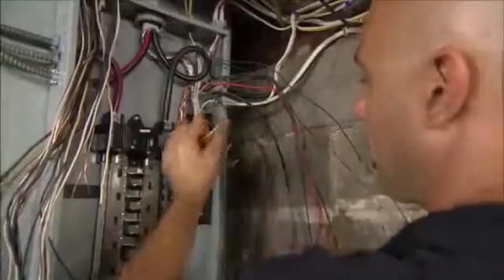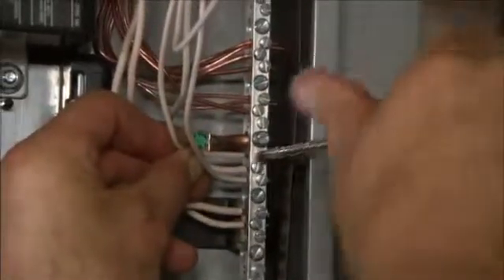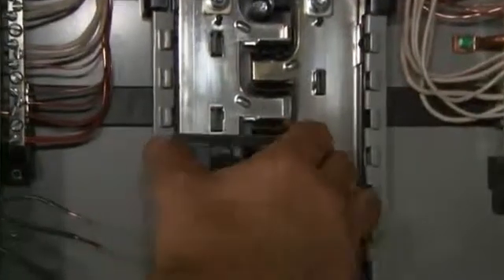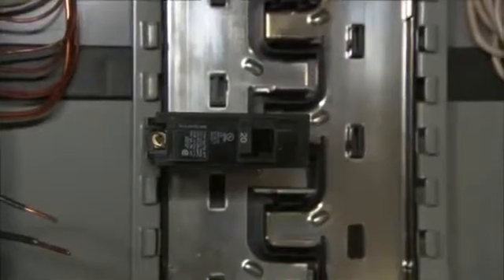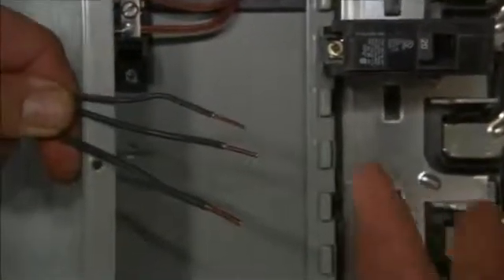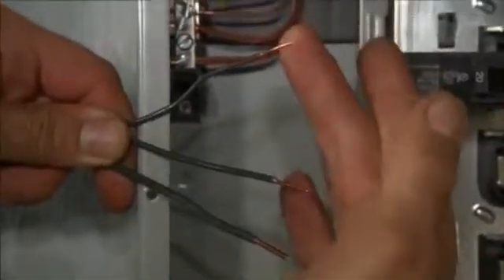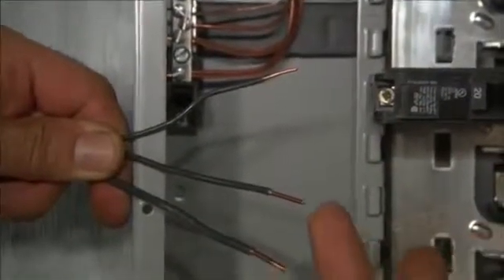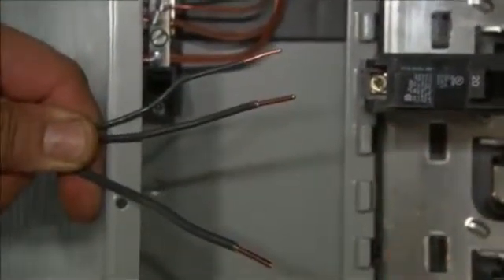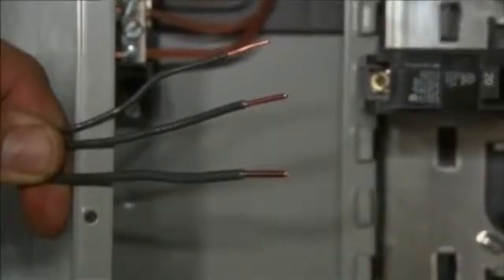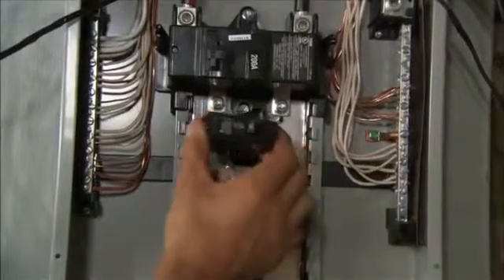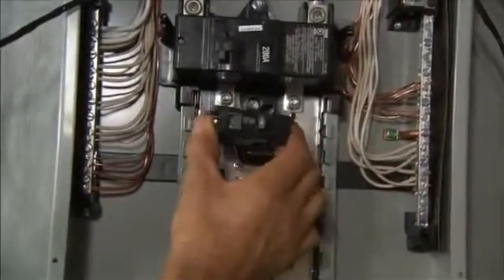Now I'm going to take the bare wires, which are grounds, and the white wires, which are neutrals, and connect them to the neutral and ground bar on the sides of the panel. Now we're ready to install the circuit breakers. Remember, the job of the circuit breaker is to prevent the wires from overheating. We have 3 different size wires that come into your electrical panel. The smallest goes on a 15 amp breaker, the medium on a 20 amp breaker, and the largest on a 30 amp breaker. Now the first circuit breaker I'm going to install is a 15 amp circuit breaker.